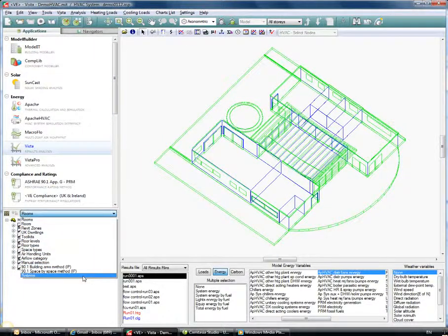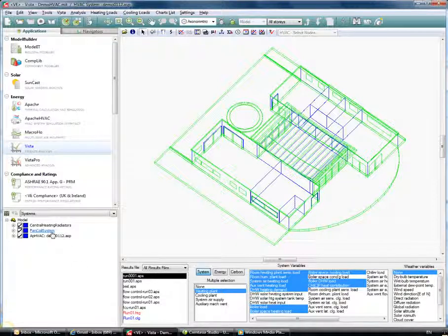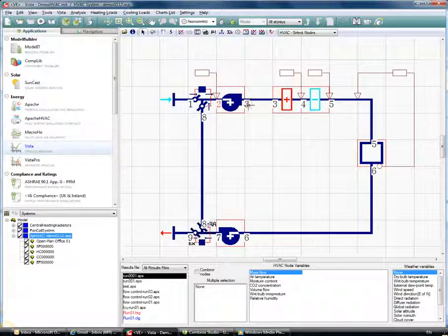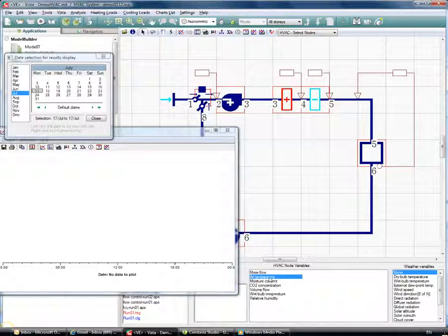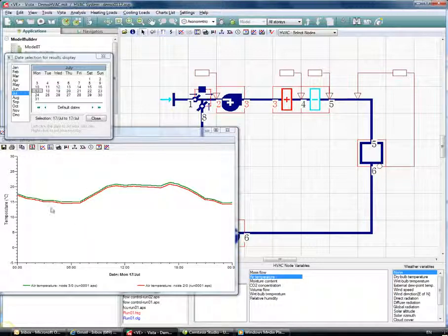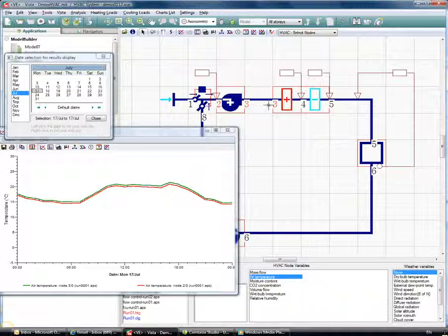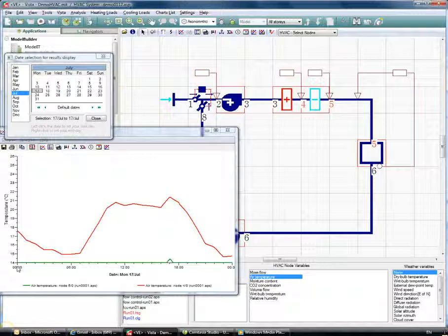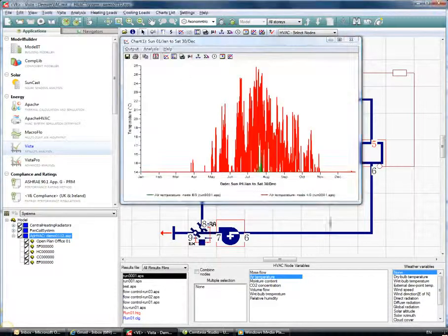Looking at air temperature before and after the fan for July 17th, we can see heat being picked up by the air from the fan — as we set, 100% of the heat pickup from the fan is available to the air, and you can see the difference. You can also see either side of the cooling coil in July: the air brought in from outside and how it's been reduced down to 14°C as expected.